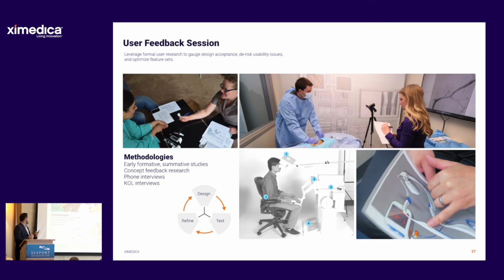So we leverage those tools early on in our concept phase, and then as the design progresses, recommend using early formative studies. Some of our products we've done 1, some we've done 3, leading up to design freeze to make sure that you've done the appropriate refinements for usability and mitigation of those use errors prior to locking the design down and moving into a final summative study.